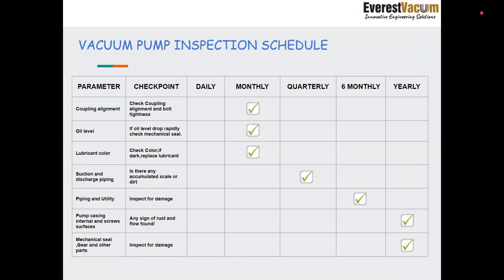Coupling alignment needs to be checked monthly. Oil level needs to be monitored monthly. Lubricant color needs to be checked. Then on a quarterly basis, we need to check the suction and discharge piping. Is there any accumulated dirt or scale that needs to be cleaned? For piping and utility, it needs to be inspected six monthly. And for yearly, we need to check the pump casing internals and screws, mechanical seal, gear, and other parts. So this is the inspection schedule that we need to follow for healthy pump operation.